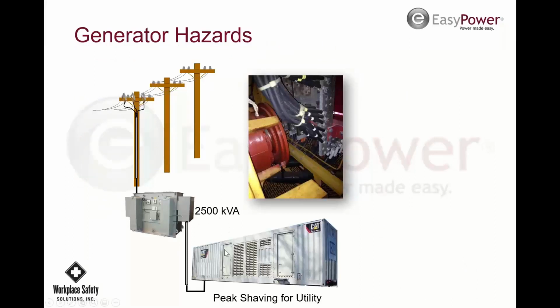This one was a generator that was set up. So this is a 2 megawatt generator. The guy had to go in the side to do some work. It's fed from a 2500 kVA transformer, and so that's fed from a pole, and it's going right through to the load side of the breaker. He didn't realize that this was live, so he shut down the breaker, shut down the e-stop on the generator, started doing some work, and got shocked on 277 volts on the feed coming from here. So he survived it, and he ended up after the shock sitting on the stairs, not knowing how he got there, and he was talking to a supervisor, didn't remember calling the supervisor, and the supervisor called 911 and got him going and all that.